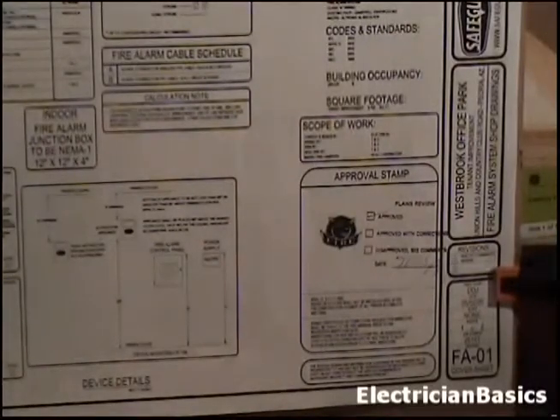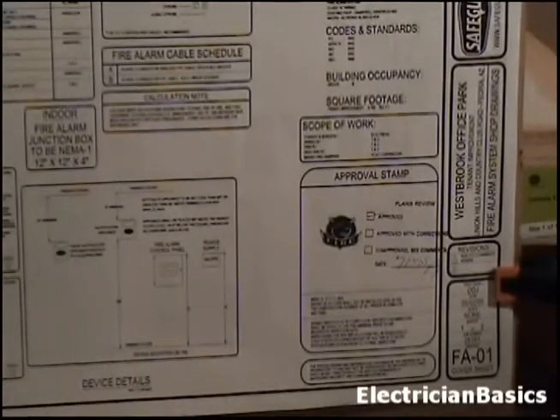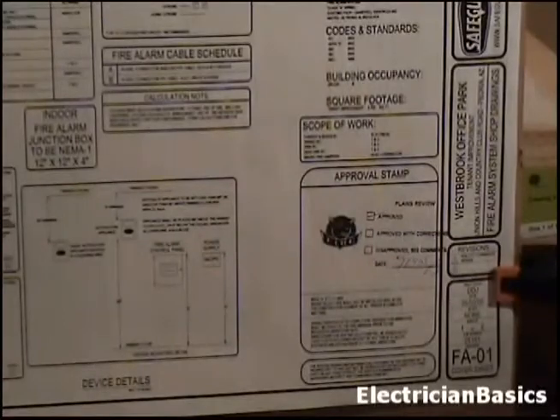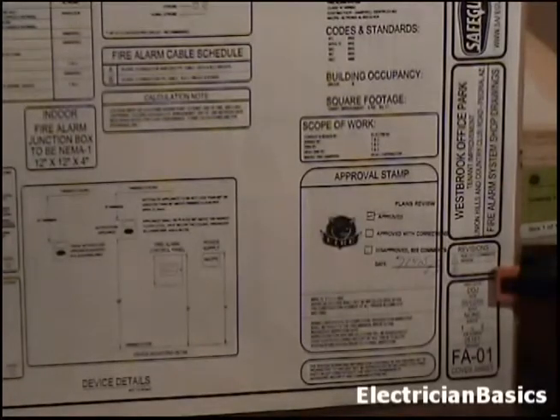Generally speaking, the electrical contractor will put in the boxes in the wall and the conduit risers out of the wall. And if it's a type of system that has to be all piped together between boxes and devices, the electrical contractor typically does that as well. And oftentimes they put a pull string in. Those are some things you have to look at, and of course if you're working with your contractor and the general contractor, they'll tell you how much of this work you're going to be doing.